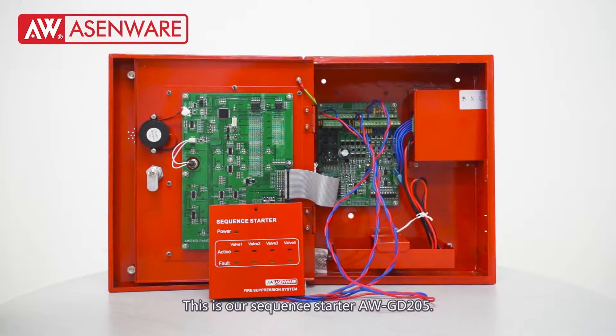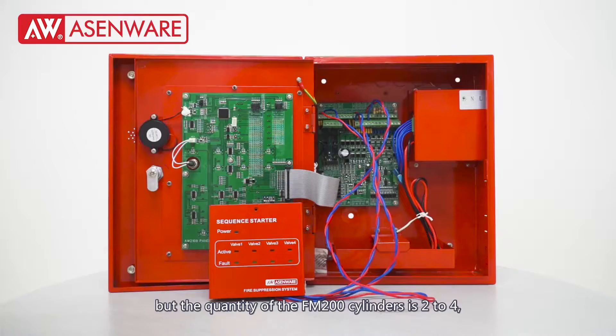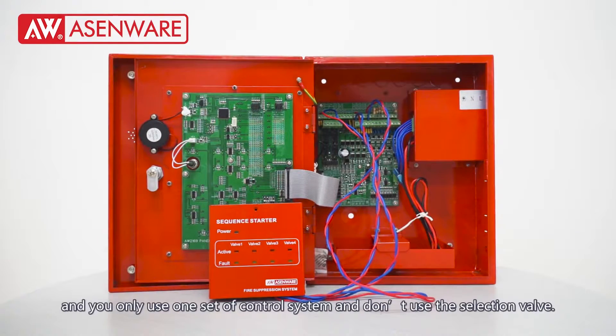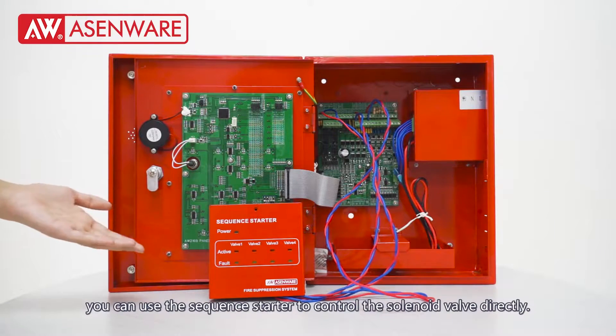Welcome to Asenware. This is our sequence starter AW-GD205. When you want to protect only one room but the quantity of FM200 cylinders is 2 to 4, or you want to protect two rooms and the total quantity of cylinders is 2 to 4, and you only use one set of control system and don't use the selection valve — in these two cases, you can use the sequence starter to control the solenoid valve directly.